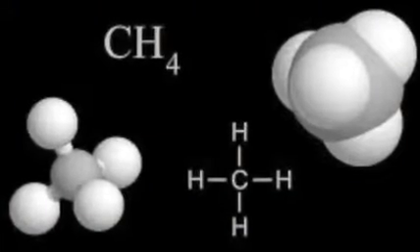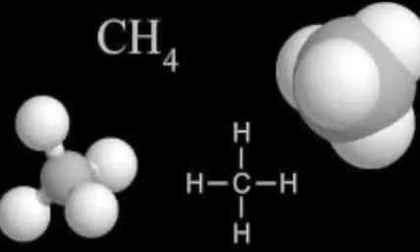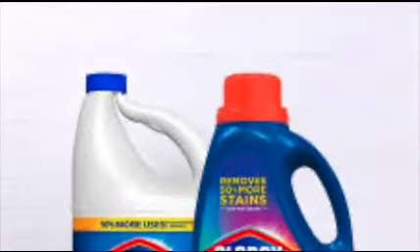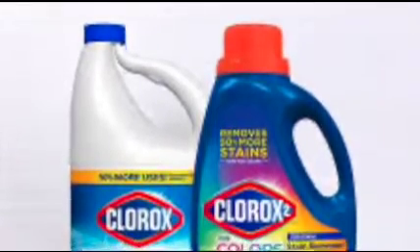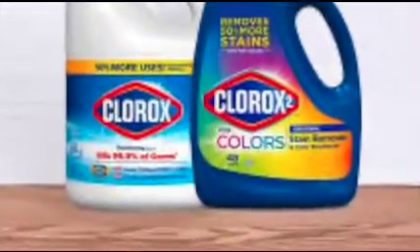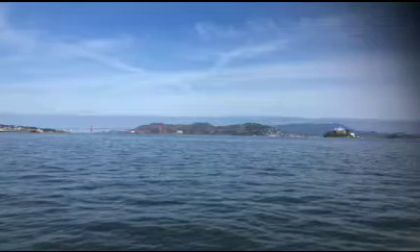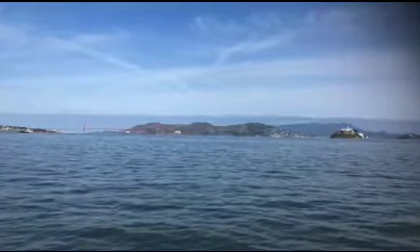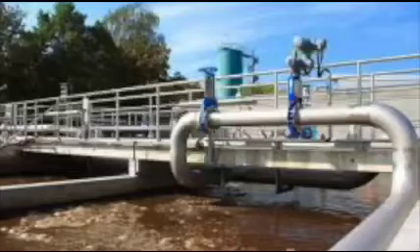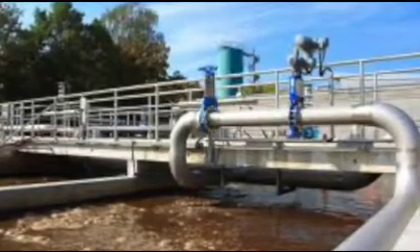The last step for the water is the chlorine contact basin, giving chlorine time to disinfect the water before it's released. This is similar to the chlorine bleach used as disinfectant in some household cleaners. Another chemical, usually sulfur dioxide gas, is added to remove the chlorine from the water prior to its final release into creeks, rivers, and oceans. We don't want the chlorine to harm the biota living in the river.